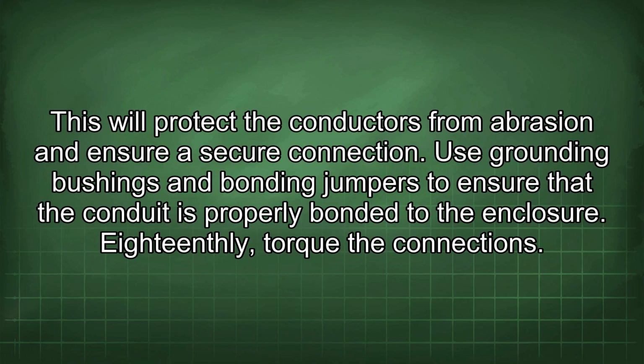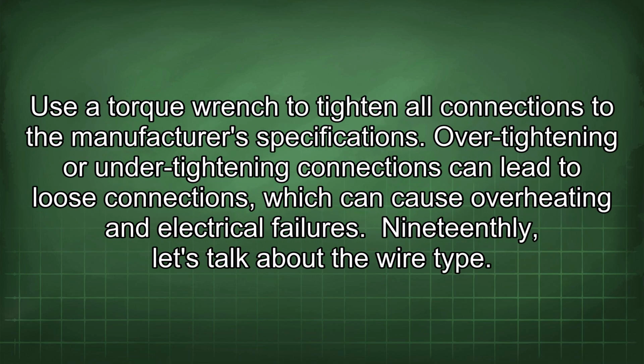Use grounding bushings and bonding jumpers to ensure that the conduit is properly bonded to the enclosure. 18thly, torque the connections. Use a torque wrench to tighten all connections to the manufacturer's specifications. Over-tightening or under-tightening connections can lead to loose connections, which can cause overheating and electrical failures.